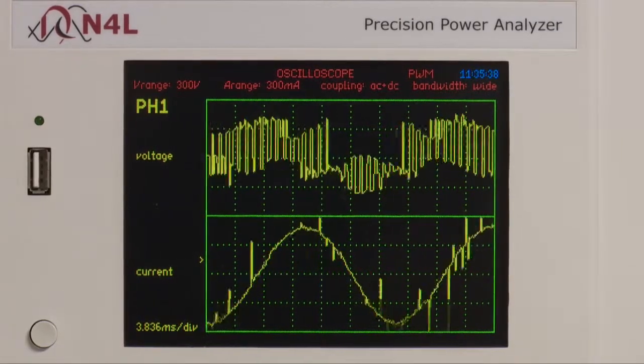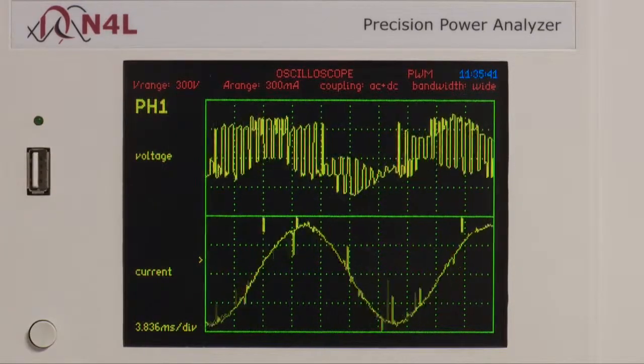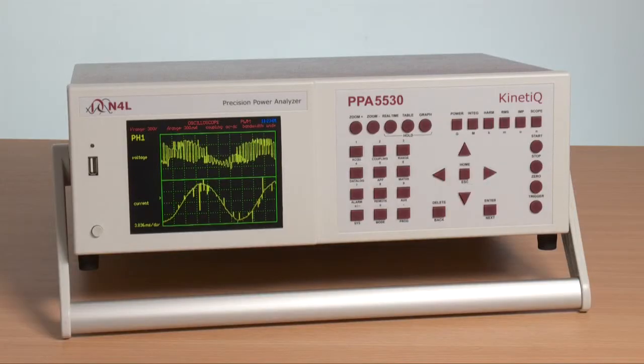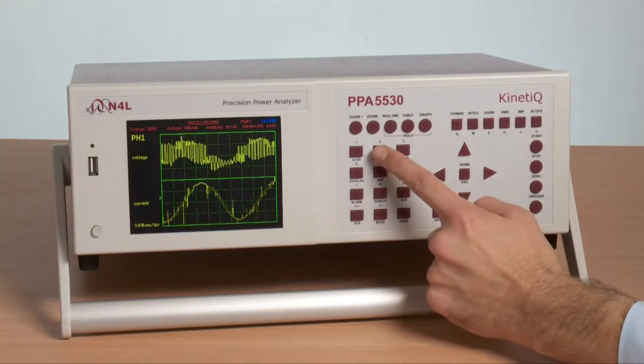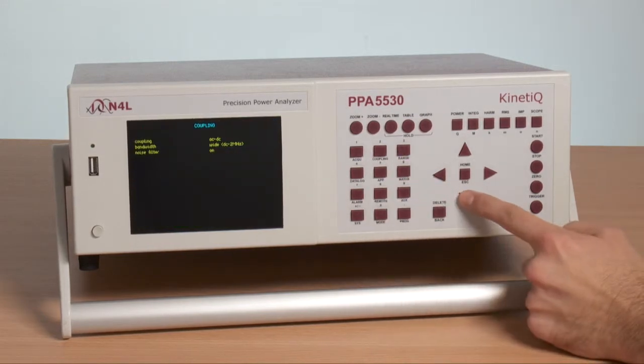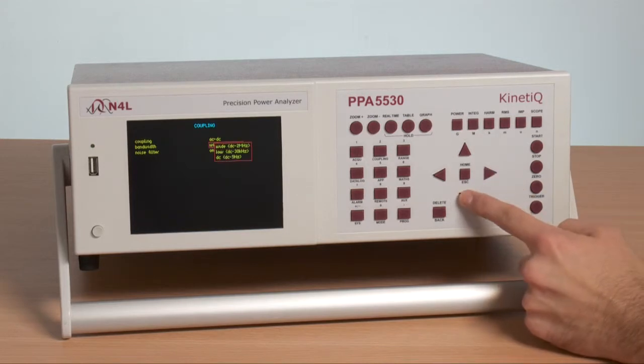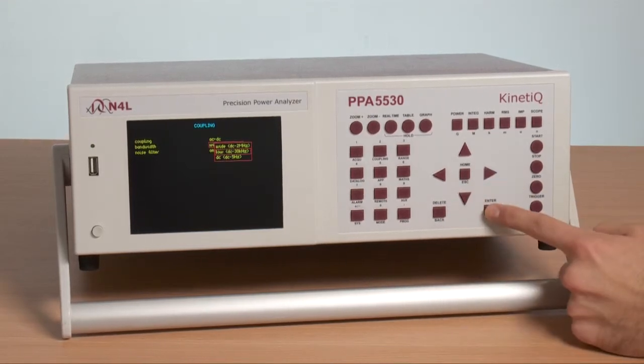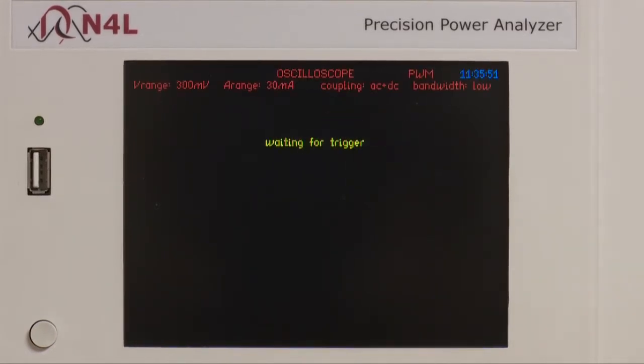The switching frequency and its associated harmonic components make detection of the correct fundamental frequency very difficult for many power analyzers. In order to solve this problem, it is quite common for measurement instruments to apply a filter that will reduce the carrier and noise. Filtering from around 30 kHz is commonly used for this purpose. By using the bandwidth function, we can apply a 30 kHz filter.